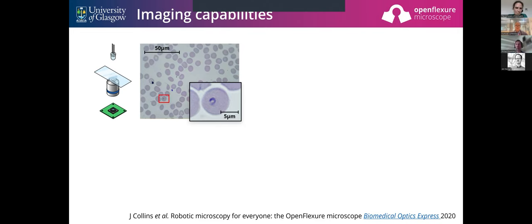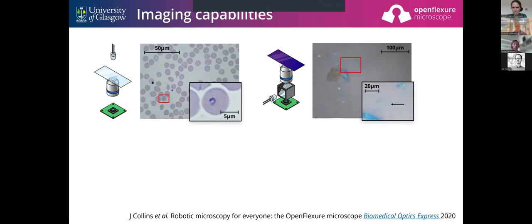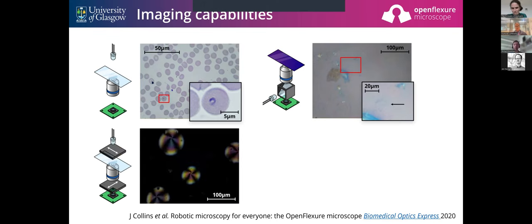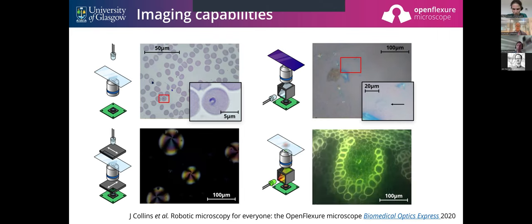The optics of the OpenFlexure microscope are actually pretty boring — it's a basic brightfield microscope, either using an upside-down webcam lens or a regular RMS-threaded objective. Most of the time we set it up in brightfield, which is typical for a lot of diagnostic microscopy. But we can also do reflection mode imaging — looking at graphene flakes, for example — stick polarizers in for petrographic imaging, or even set it up in fluorescence, although the fluorescence has never been quite as polished as I'd have liked. That's still a work in progress.